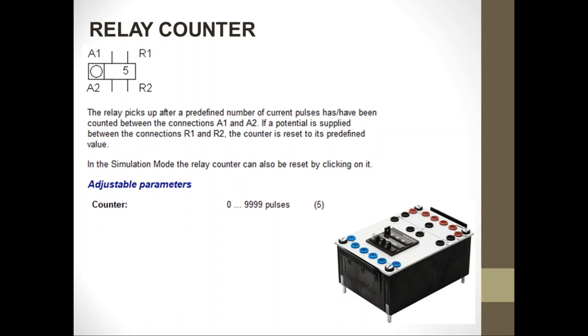The relay counter, unlike the timer, does not provide time delay — it counts. The function of the relay counter is to count the number of pulses that the coil receives. The term 'pulses' is related to turning on and off, meaning the relay counter counts the number of times the coil has been turned on and off.